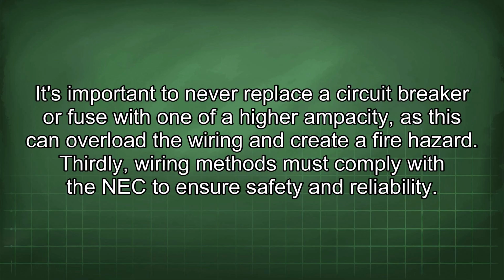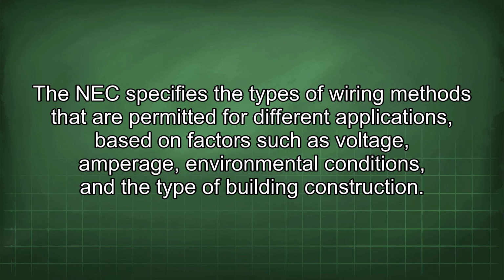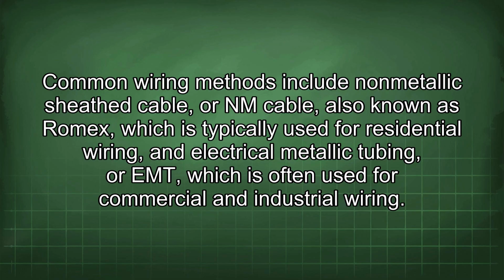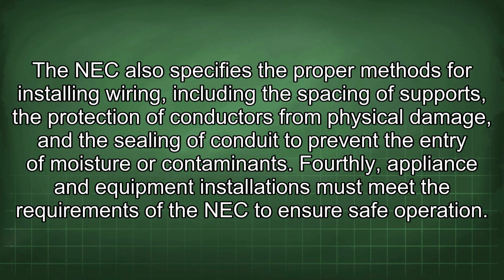Thirdly, wiring methods must comply with the NEC to ensure safety and reliability. The NEC specifies the types of wiring methods that are permitted for different applications, based on factors such as voltage, amperage, environmental conditions, and the type of building construction. Common wiring methods include non-metallic sheath cable, or NM cable, also known as Romex, which is typically used for residential wiring, and electrical metallic tubing, or EMT, which is often used for commercial and industrial wiring. The NEC also specifies the proper methods for installing wiring, including the spacing of supports, the protection of conductors from physical damage, and the sealing of conduit to prevent the entry of moisture or contaminants.